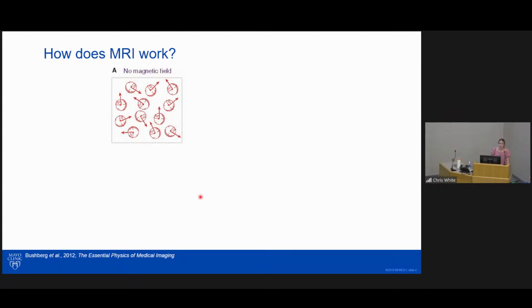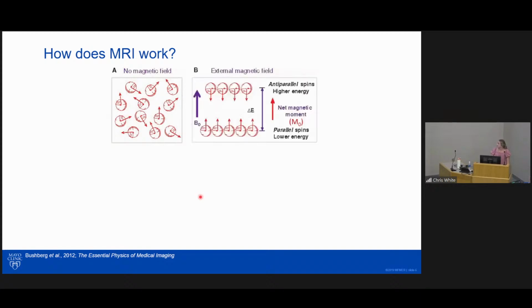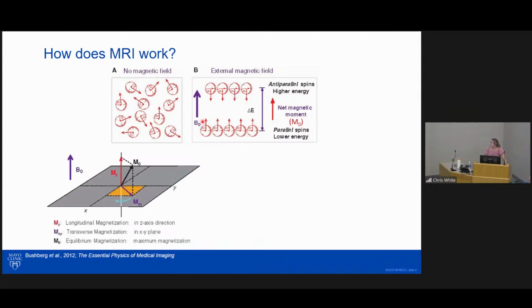Once placed in a strong static magnetic field, the protons are either going to align in the parallel direction or the anti-parallel direction with respect to that main static field B0. And then a slight majority of the protons are going to exist in the parallel state, which is going to create a net magnetic moment called M0 that's going to be parallel to the B0 field. We then apply a B1 pulse perpendicular to the B0. So this causes the magnetization vector M0 to flip down into the transverse plane.